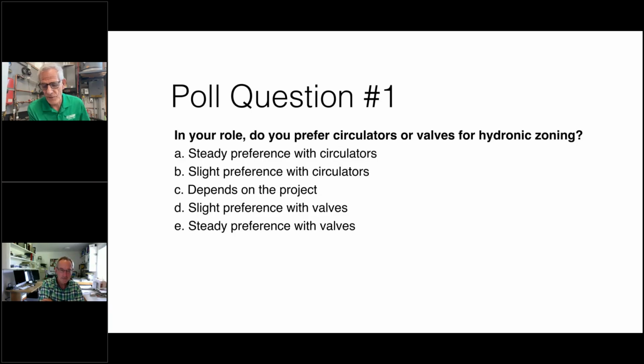Yeah, and I don't think there will ever be an exact answer to that. I mean, sometimes it's personal preference. Sometimes you've got to look at a lot of different requirements of that system to make that good decision. When I see a circuit where it's a kitchen circuit that's got a 15,000 BTU load on it, and it's got its own pump, really, where's that pump operating on its curve? Probably right off the bottom of the curve, trying to move 1 GPM through a circuit with even the smallest circulator money can buy.